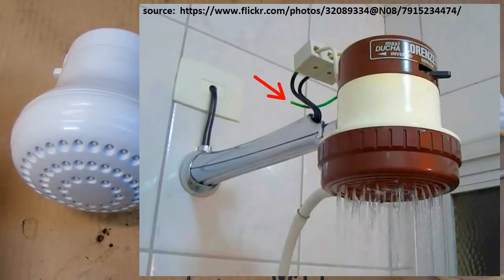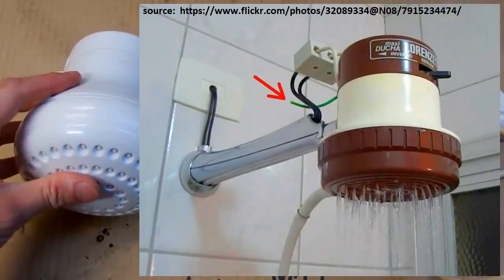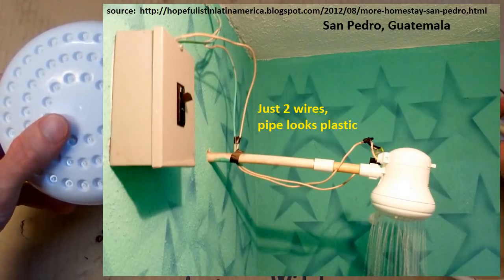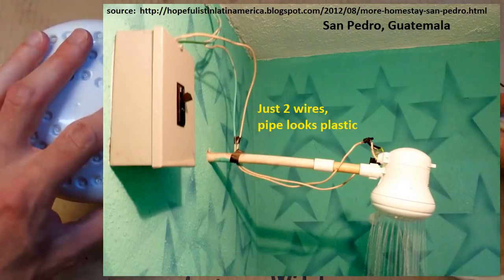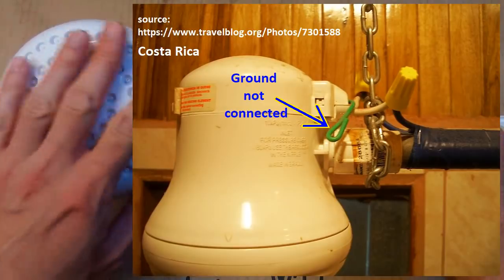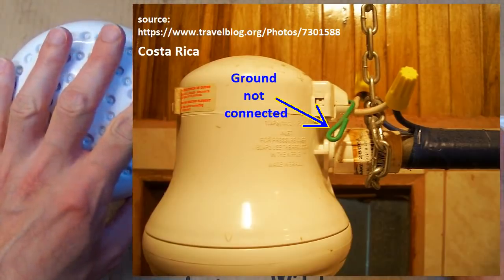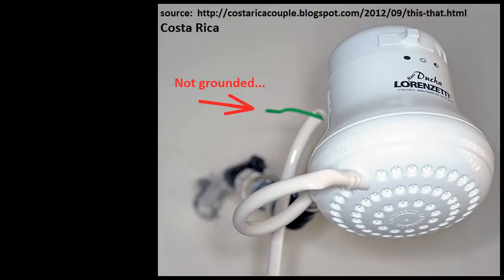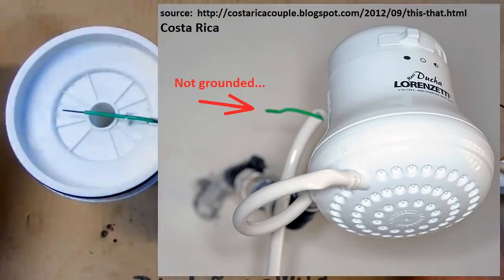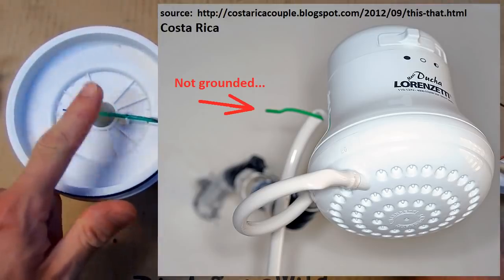So I tested it in both situations. Grounded and not grounded. And it turns out that if it's grounded properly it's almost impossible to get a shock from it. Even if your body is grounded and you touch the nozzles directly you probably don't get a shock. Because the voltage in the water at the nozzles is very low. Thanks to this grounding electrode at the outlet.